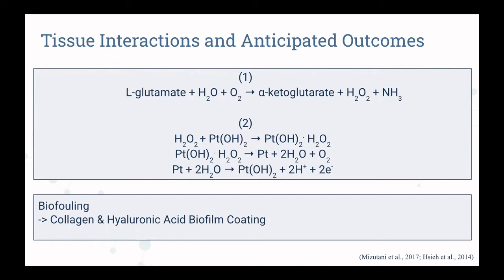The immobilized glutamate oxidase layer of the working electrode will catalyze the reaction in the first equation when glutamate is present in the biofluid in the brain. The platinum polymer layer of the working electrode would then utilize the hydrogen peroxide produced from the enzymatic catalysis reaction. The platinum nanoparticles would oxidize the hydrogen peroxide through a reaction in the second set of equations. The result of this reaction creates an anodic current where electrons are entering the electrode. The number of excess electrons entering the electrode is proportional to the number of glutamate molecules in the biofluid.